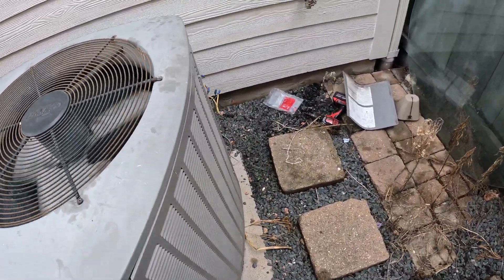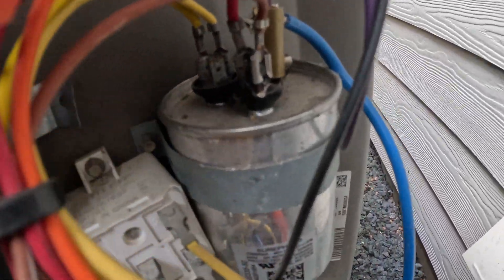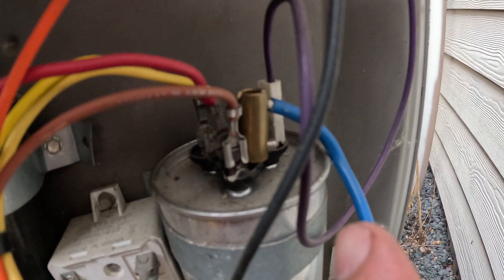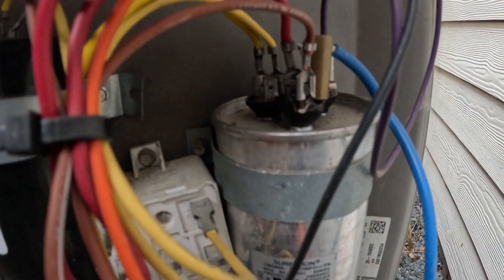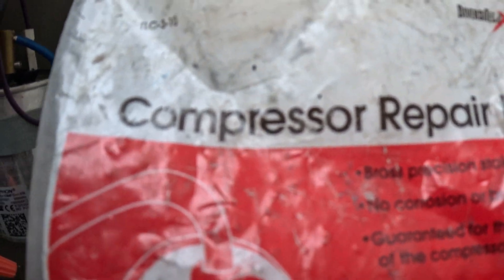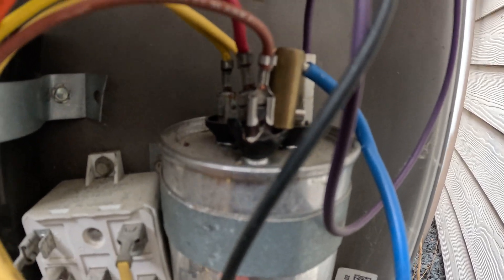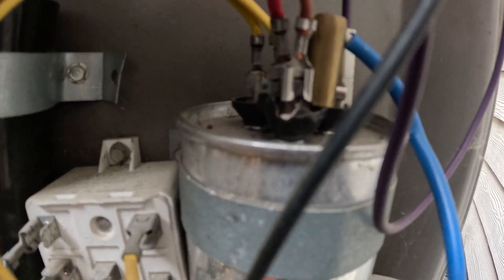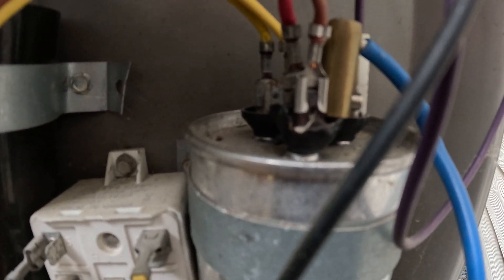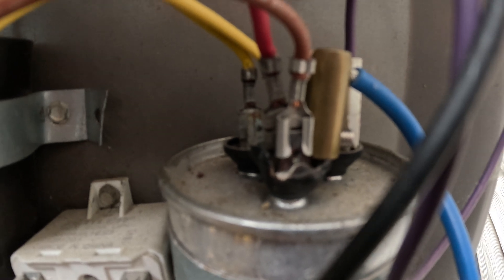On this video, we're going to talk about wires burning out on the capacitor unit. About three years ago I actually installed that wire there. You can put a compressor repair kit on your capacitor wires when they start burning off. Most technicians — I actually haven't seen a technician do this — but what will happen is when your wires start burning off on your capacitor, they'll usually burn off like every three months or six months.